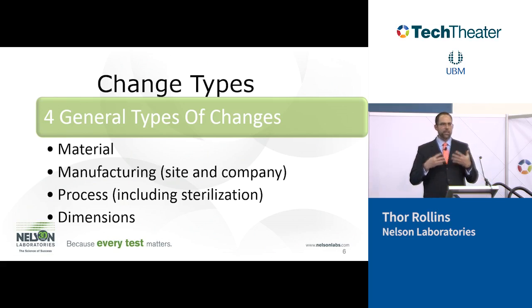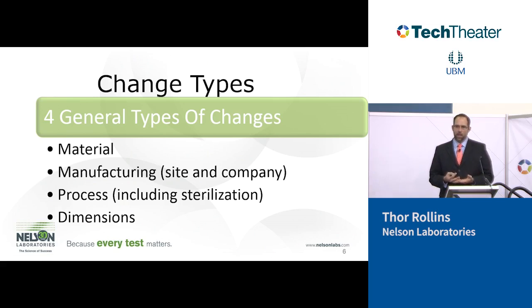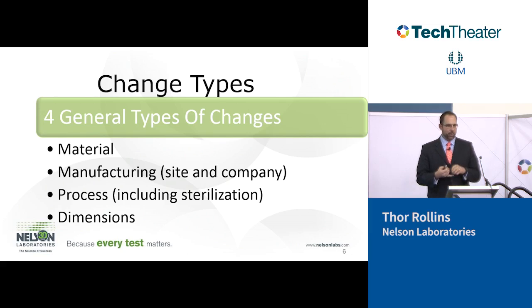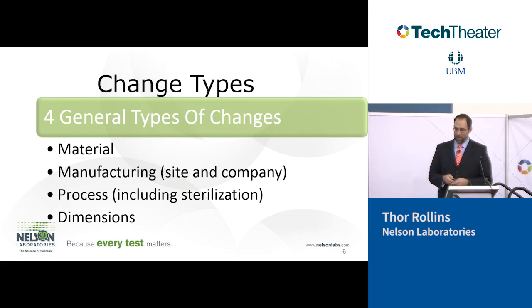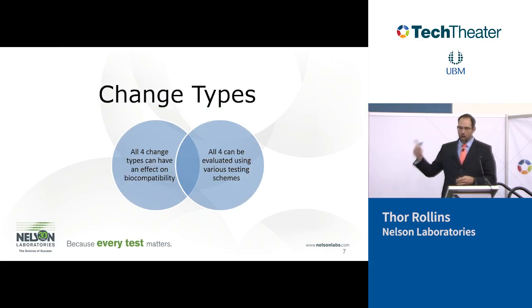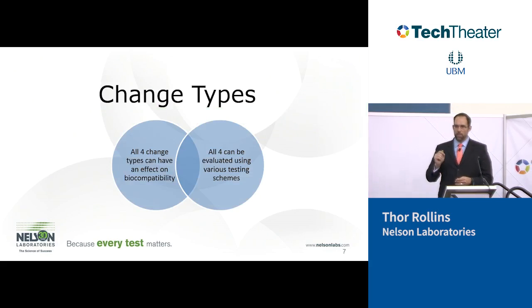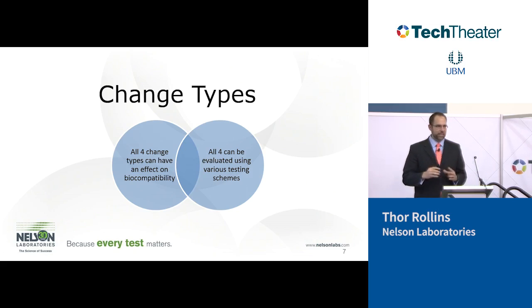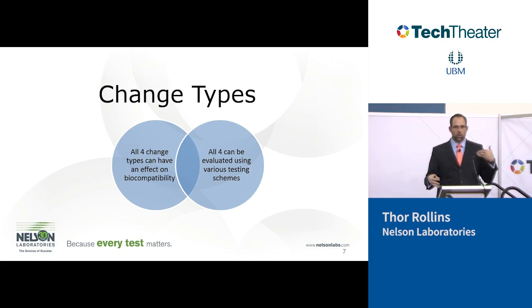A lot of people think that a dimension of a medical device may not have a big impact in the body. But when you're looking at hemocompatibility or implantation, the dimensions of the device can have a huge impact. So even though the materials and processes may stay the same, if you're changing the overall dimensions of a medical device and it has implantation or hemocompatibility involved in it, then those changes can have an impact in the biocompatibility, or potentially can. So these are the 4 changes that we generally see with medical devices at Nelson Labs. All 4 of these changes we can evaluate with minimal testing. And I'm going to help you go through a decision process that we use internally to help decide the impact of a change, and then some of the testing that we use to evaluate the potential of that change.